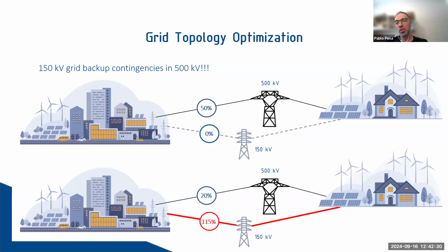Another promising solution is grid topology optimization. By making topology changes at the high voltage level, we can alleviate some of the congestion by switching lines off. But there is always a but. Nowadays, the 150 kilovolt grid also serves in Uruguay as a backup for contingencies in the 500 kilovolt system. So in our case, meshing the extreme high voltage grid network is crucial to enable this option of power flow redirection.